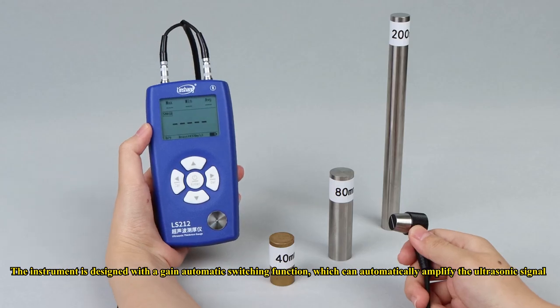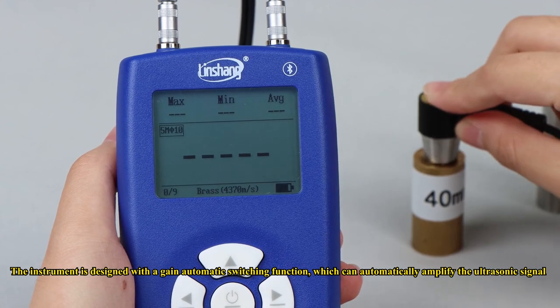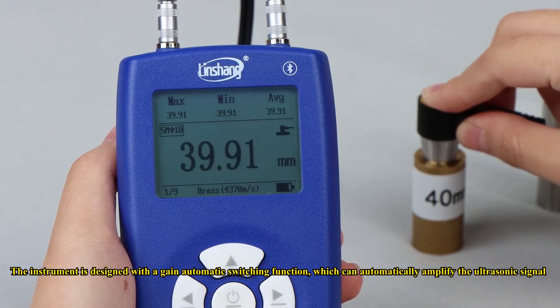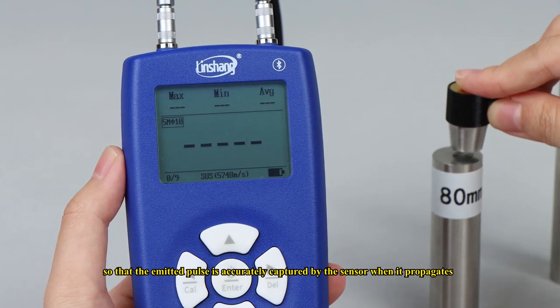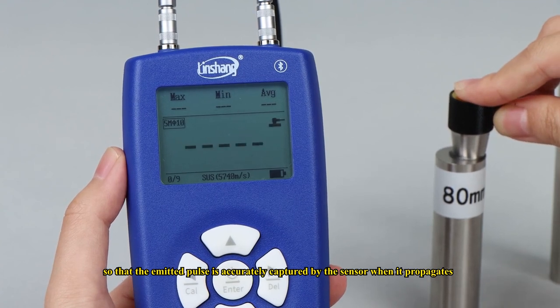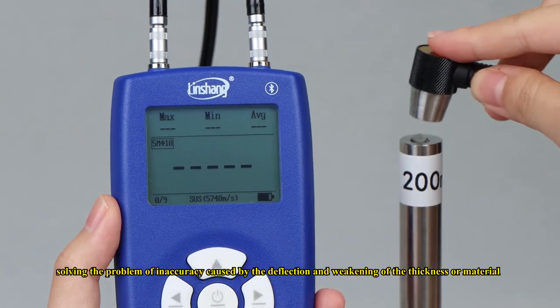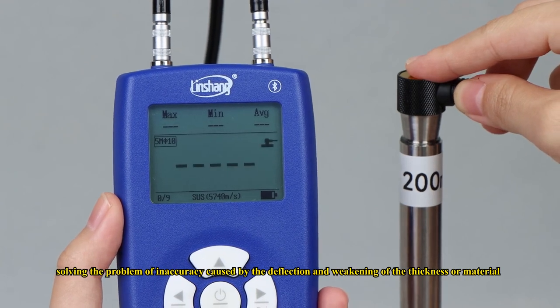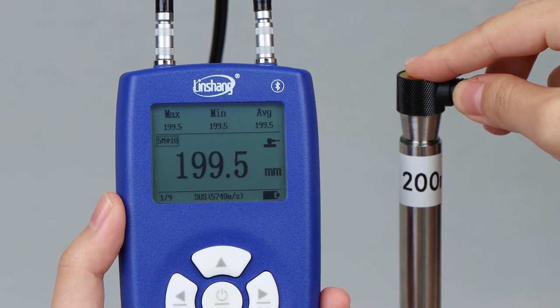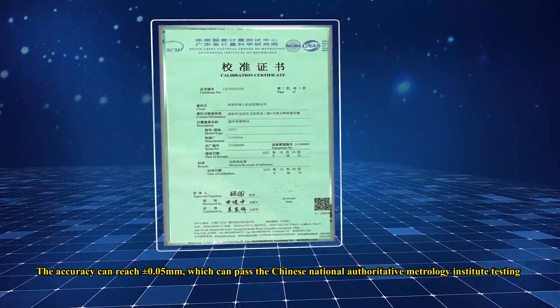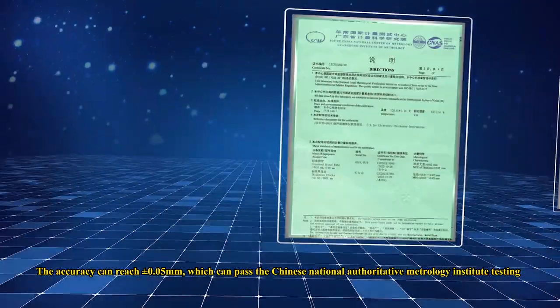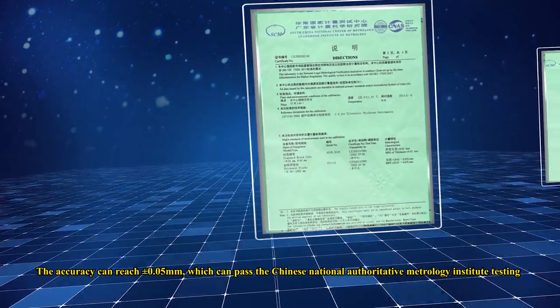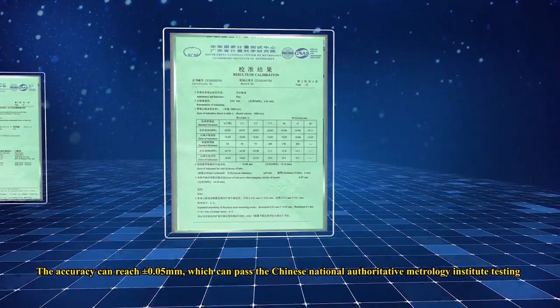The instrument is designed with a gain automatic switching function, which can automatically amplify the ultrasonic signal, so that the emitted pulse is accurately captured by the sensor when it propagates, solving the problem of inaccuracy caused by the deflection and weakening of the thickness or material. The accuracy can reach plus or minus 0.05 mm, which can pass the Chinese National Authoritative Metrology Institute testing.